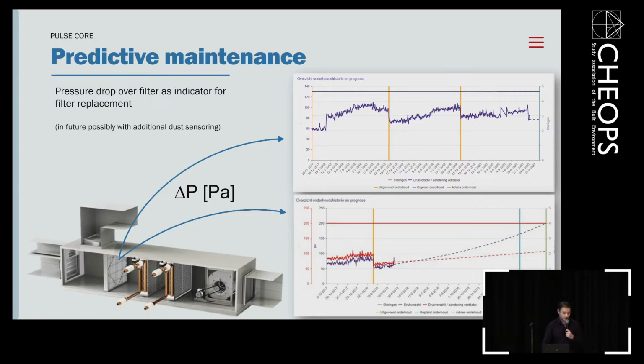Something else for predictive maintenance is the filters in air handling units, which have to be replaced regularly. Over time they get polluted, and by measuring the pressure drop over a filter you can determine when it's time to replace it. You can also predict it, though this is no longer a linear relationship but an exponential one, allowing you to determine when you'd expect to need to change these filters.